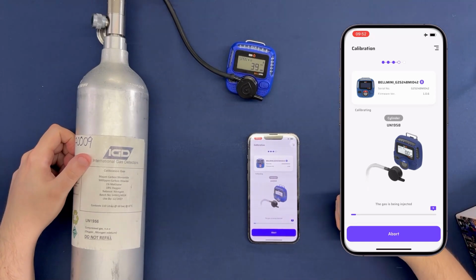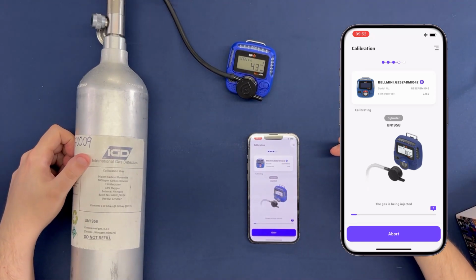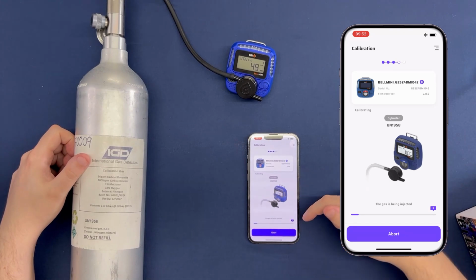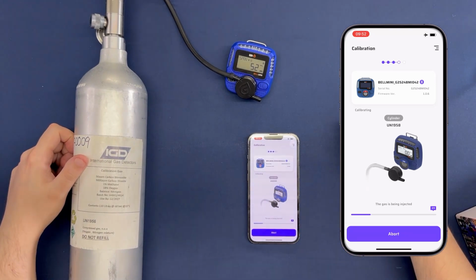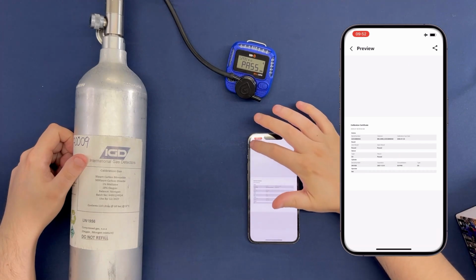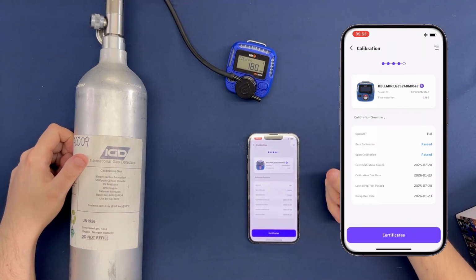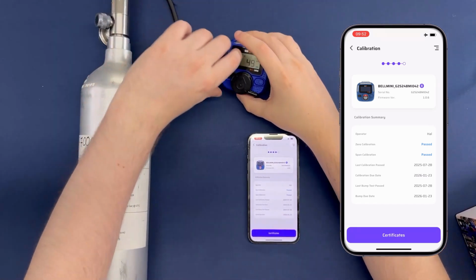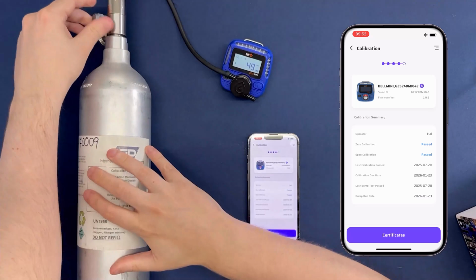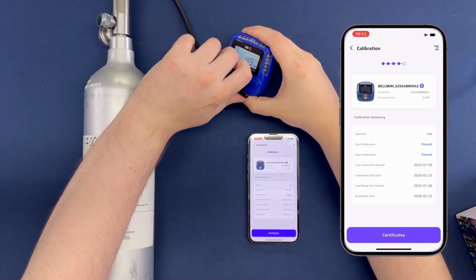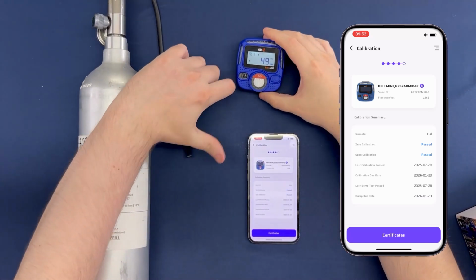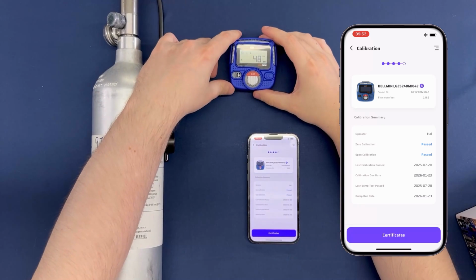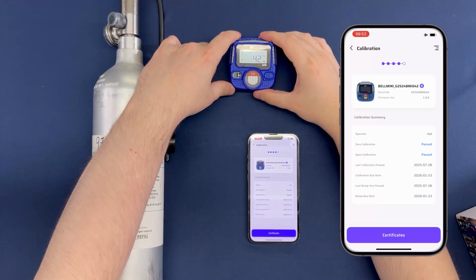So it is software driven. It is looking at the sensor response time and the gas and the reading. And as you can see, there's a little timer at the bottom. So as we can see, the portable passed its calibration, and we can see here 0 pass, span calibration passed. And the portable will go into alarm, so we just turn the gas bottle off and take the calibration adapter off. And as you can see, the readings will go down.